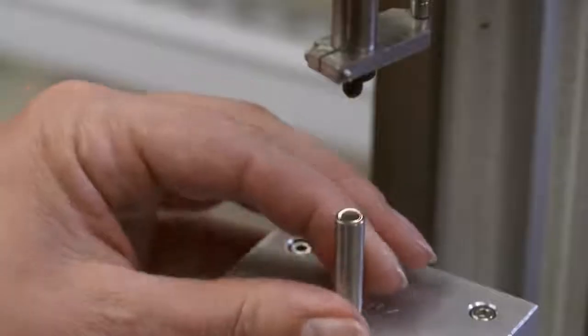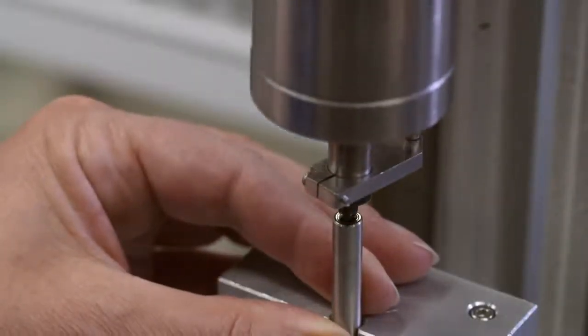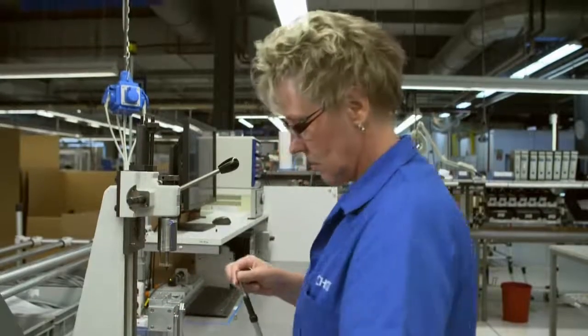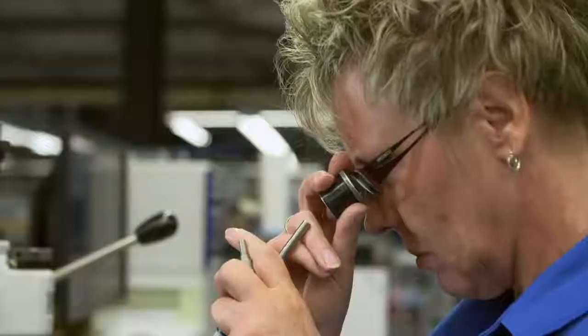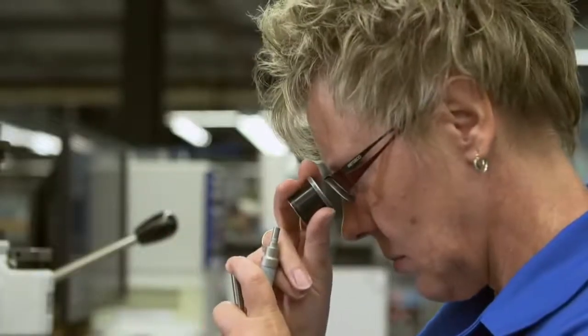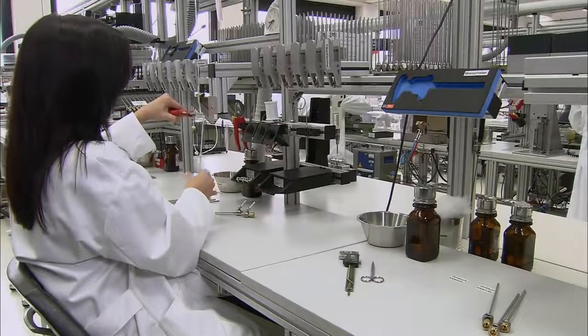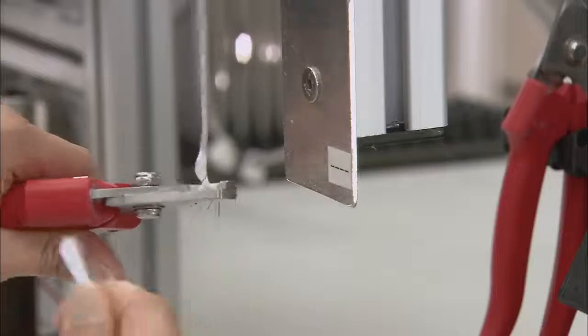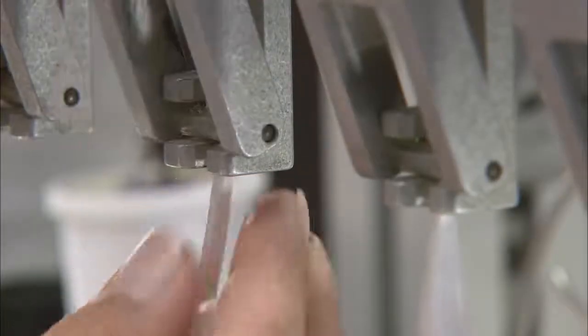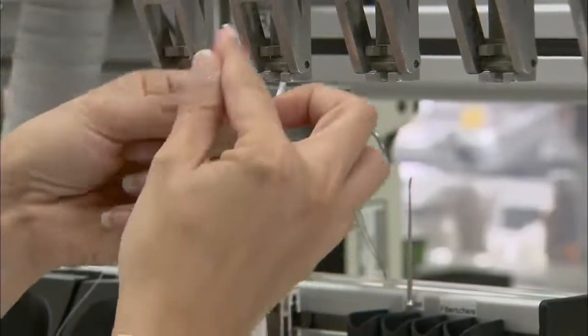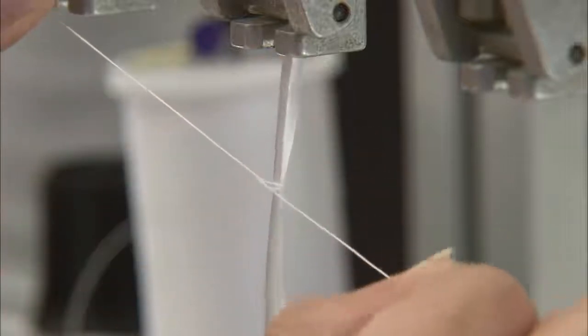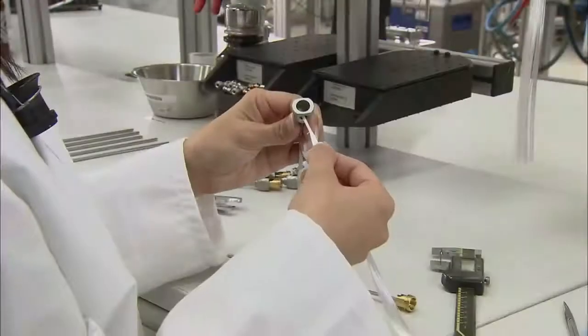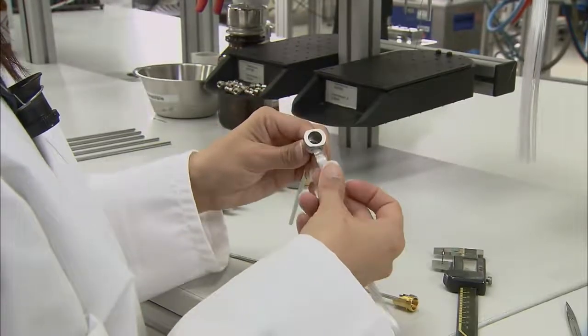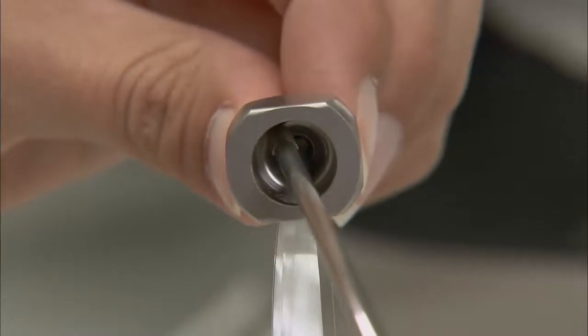An initial quality control test ensures that the fibers can withstand a prescribed amount of pressure without cracking. Spools of optical fibers are also used to construct the light transmission system inside the endoscope. To do this, a bundle of optical fibers is first cut to the correct length for the endoscope model being produced. Endoscopes vary in length and diameter, depending on the part of the body they're designed for. After verifying that the bundle is the correct diameter, the optical fibers are tied with string to hold them together. The fiber bundle is then inserted between the inner and outer stainless steel tubes that make up the main body of the endoscope.